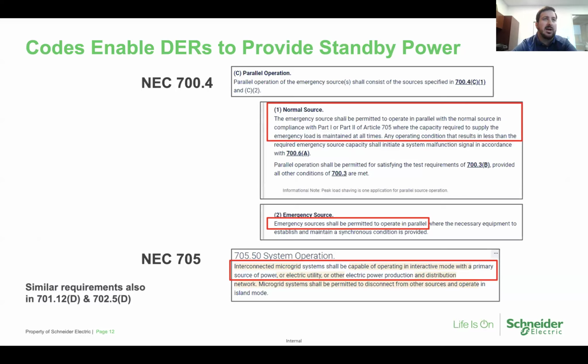And that goes back to the point I made before about people wanting more than just resiliency from their emergency source. They also want to use it for economic optimization. So the code is allowing this. That's one major shift that's happened over the years. First, that the code allows you to use your standby power source for more than just standby power. You can use it in parallel with utility so that, for example, with a battery energy storage system, you can charge that system from your excess solar or when power is cheap, and then discharge it when it's expensive, which helps you save money by basically playing the utility rates against each other and save money and economic optimization through that method. So the first most important thing is people are now allowed to use renewable sources and distributed energy resources for standby power, and they're allowed to use it in parallel with utility, which is what you're going to want to be doing 99% of the time when you don't have an outage, to help you save money off your utility bill in the long run.